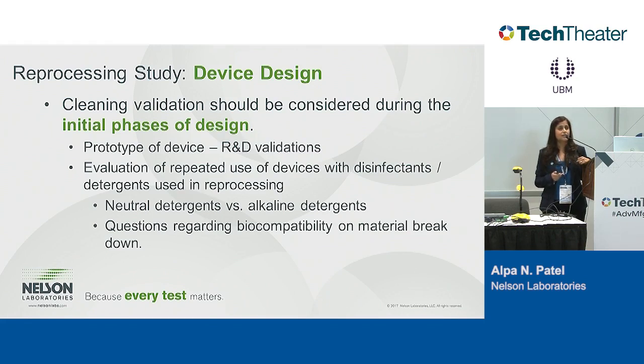A lot of the times, the validations are performed with neutral pH detergents, but as you know, Europe, for reusable medical devices, uses alkaline. And when they use alkaline, it breaks the devices apart more than it would with neutral pH. So things like that also should be considered for reprocessing.